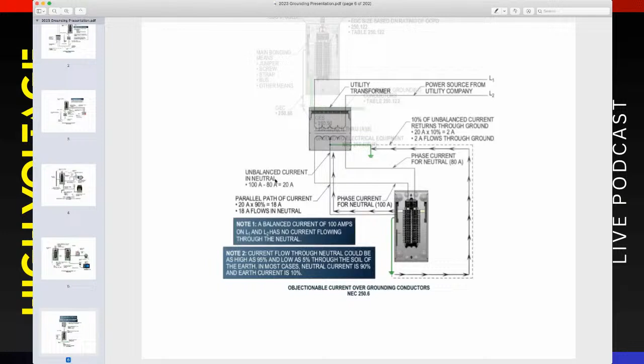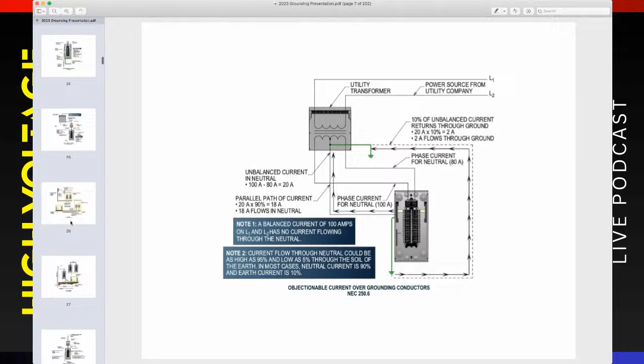We actually get into that when we get over to 250.96, and also tie it in with 250.146D. We even show an example here with an illustration of how to calculate that fault current. This is a full breakdown—we tell you our grounding electrode is at 5 ohms, which comes from the IEEE Green Book.